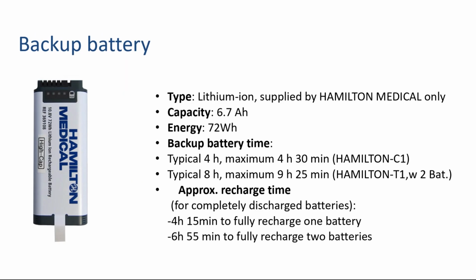The Hamilton T1 can be operated with one or a maximum of 2 lithium-ion batteries. Each battery has a capacity of 6.7 ampere-hours and provides 72 watt-hours. The backup operating battery time with 2 fully loaded batteries in a Hamilton T1 is typically 8 hours. The approximate recharging time for completely discharged batteries is 7 hours when 2 batteries are inserted at the same time.